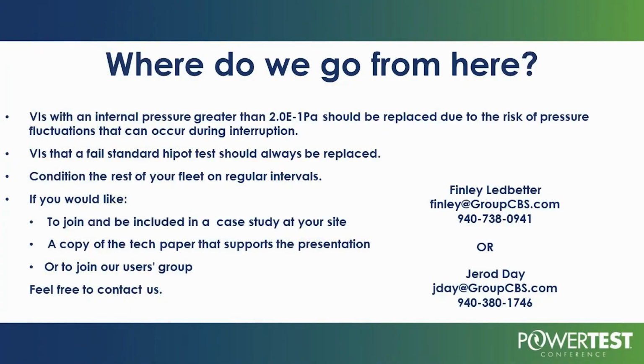Always make sure you take care of the lubrication. That's the number one killer. The number one killer in these breakers is not loss of vacuum pressure, it's lubrication. Never forget that. Inactivity and lubrication is your number one enemy. Moisture is number two. We have a technical paper that follows this that gives you a lot more detail.